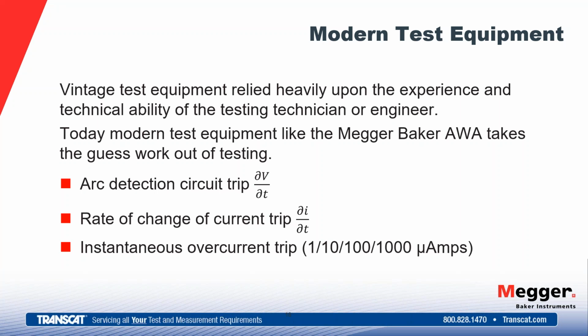Instantaneous overcurrent trip. It has trip settings and is able to, again, stop the test if at any point it detects an overcurrent trip. And on the surge, we also have what we call the pulse-to-pulse EAR. We're looking for wave instability. If that waveform becomes unstable, it trips the tester and we stop the test at that point. So these safety measures are built into the testing that weren't always there with older equipment.